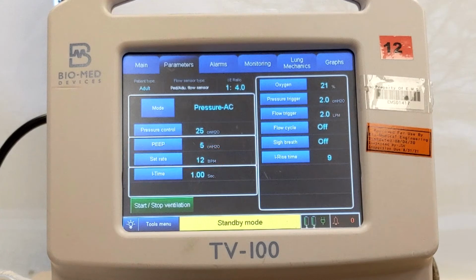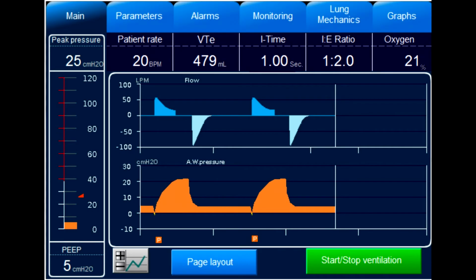The current mode selected is using pressure control. The TV-100 delivers flow as needed to maintain the set pressure for the duration of the inspiratory phase. The set pressure will be referenced to PEEP. This figure illustrates a TV-100 pressure control waveform, as well as a patient-triggered breath, designated with the P below it.